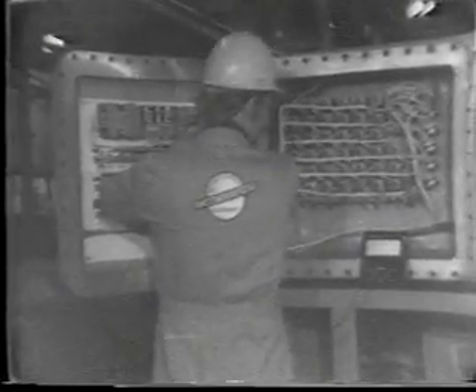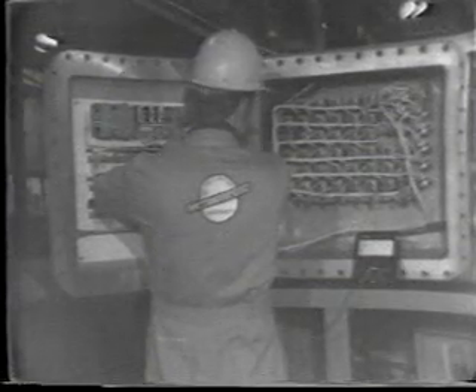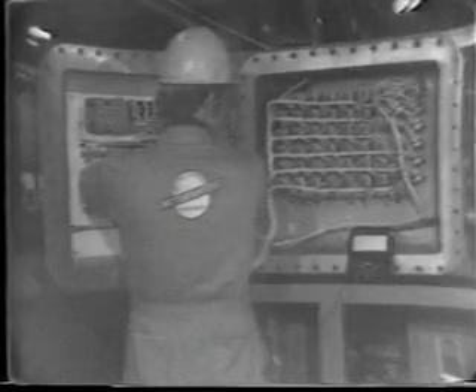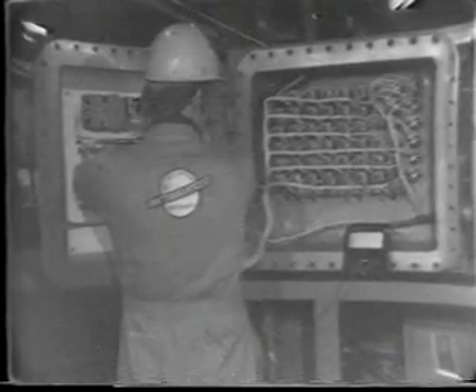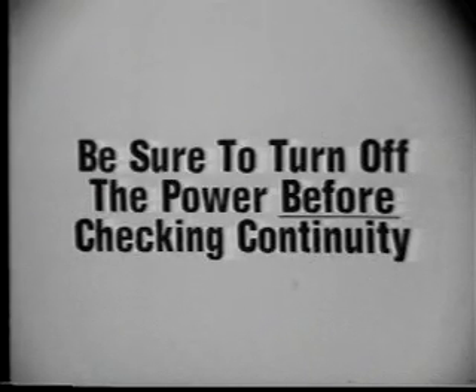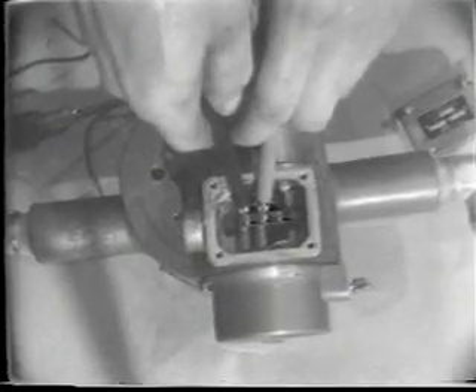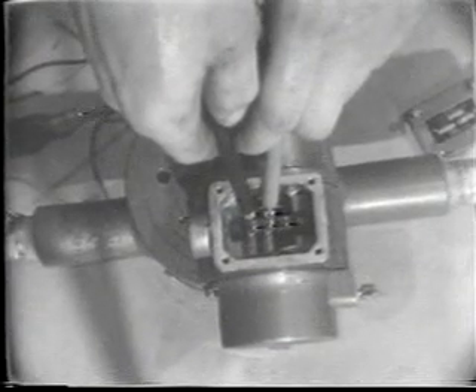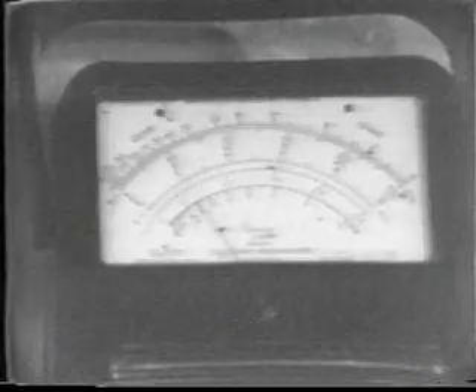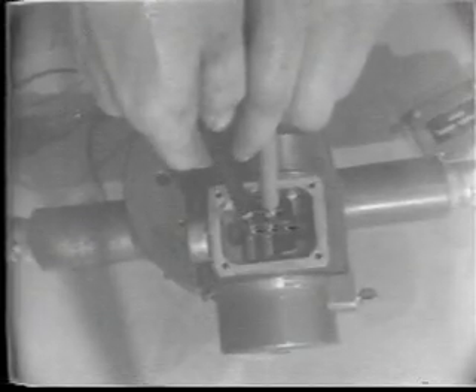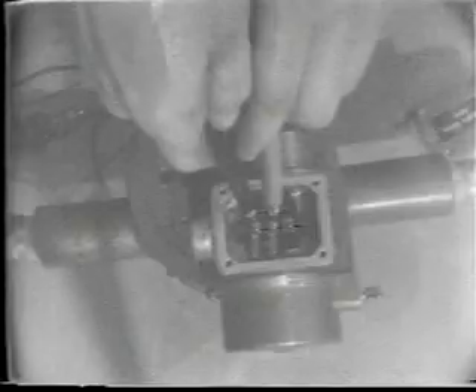If you read no voltage or a constant voltage, then the relay, the coil, or the magnetic reed switch in the flow meter on the hydraulic control manifold is bad. To check the reed switch in the flow meter on the hydraulic control manifold, first turn off the power to the system. Remember to isolate the batteries so that there is no voltage to the system. When you have turned off the voltage, remove the terminal block cover and start a slow fluid flow through the system. Now you can check the terminals for a pulsating continuity. If the continuity does not pulsate, then the reed relay switch must be replaced.